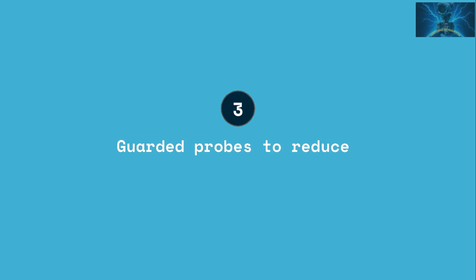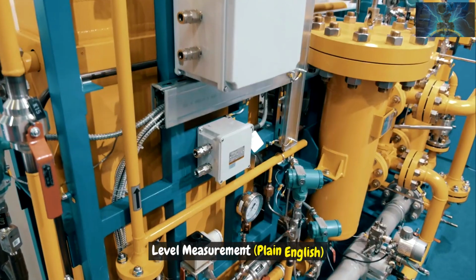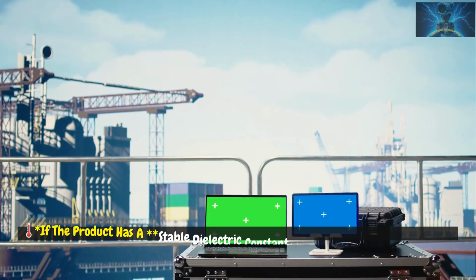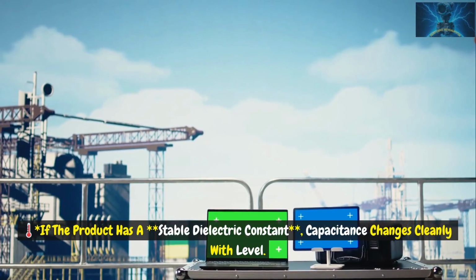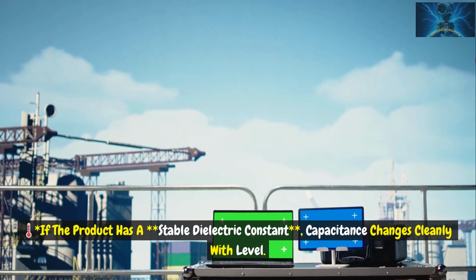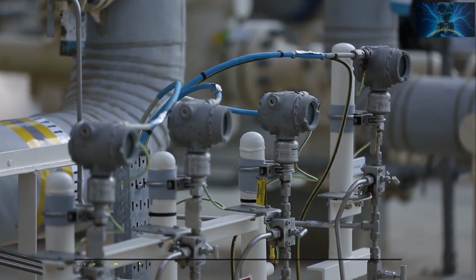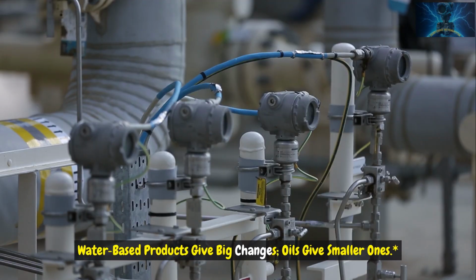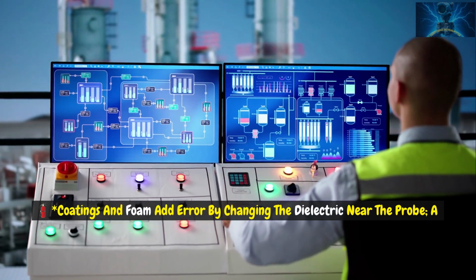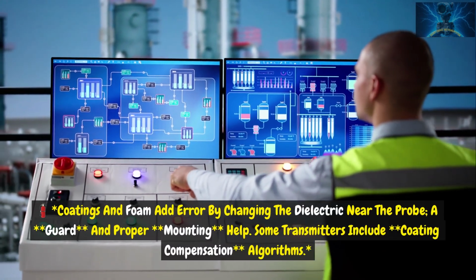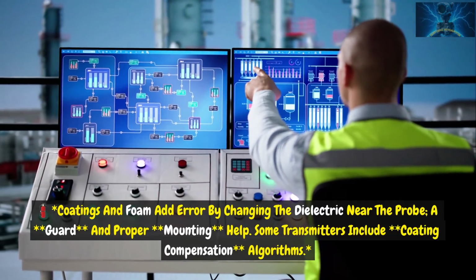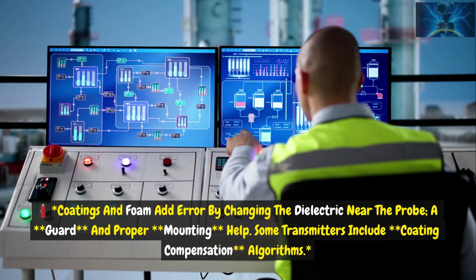Guarded probes use a driven guard sleeve to push the field into the material you care about and reduce stray effects. Level measurement, plain English. If the product has a stable dielectric constant, capacitance changes cleanly with level. Water-based products give big changes. Oils give smaller ones. Coatings and foam add error by changing the dielectric near the probe. A guard and proper mounting help.